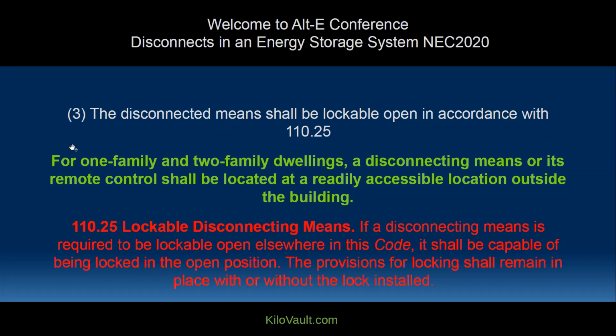One key thing in the code that I think is going to get a couple inspectors pushing a lot harder is that they're going to require, for one-family and two-family dwellings, a disconnect means or its remote control shall be located at a readily accessible location outside the building. I've already had several customers with inspectors requiring this, even though you're below 60 volts at this point. Say you're using an AGM or lithium battery with a max voltage of say 56 to 58, inspectors are still requiring that disconnect outside with a placard showing that it's a disconnect for energy storage.